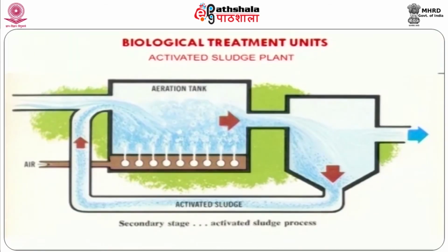At the same time, if you provide more solids retention time, we can promote the growth of carbon oxidizing heterotrophic bacteria as well as nitrifying autotrophic bacteria. Another aspect while designing the configuration of the reactor is sludge volume index. That is a crucial parameter to evaluate the settling behavior of mixed liquor suspended solids. In most cases the sludge volume index value should be within 120. In this way only we can easily segregate mixed liquor from the aqueous phase, otherwise we need coagulant to remove solid particles that will be generated during aerobic transformation.